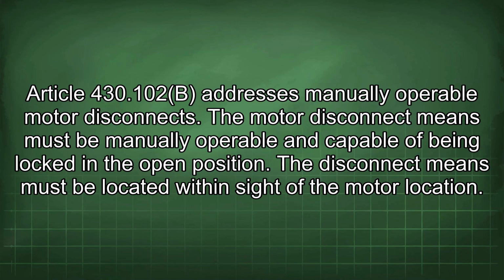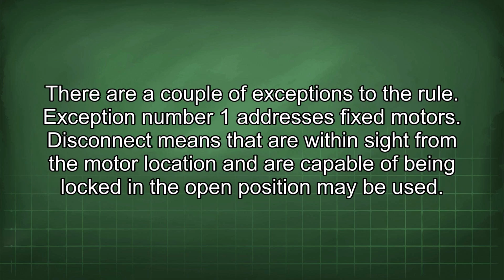430.102(b) addresses manually operable motor disconnects. The motor disconnect means must be manually operable and capable of being locked in the open position. The disconnect means must be located within sight of the motor location. There are a couple of exceptions to the rule.